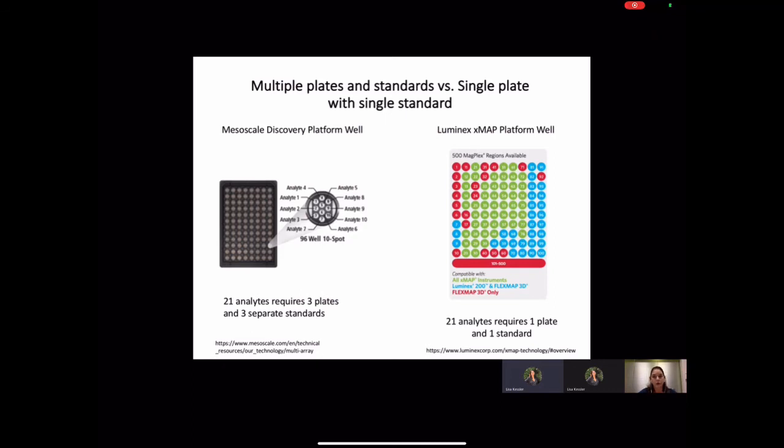On the right is the bead region map for the Luminex XMap platform. It requires one standard black-walled 96-well plate in which all 21 beads or analytes can be mixed together in a liquid suspension. One well has the potential to hold 100 or more different analytes. The user just needs to add the sample, an assay buffer, and the pre-mix beads, and then begin the incubation on an orbital shaker.